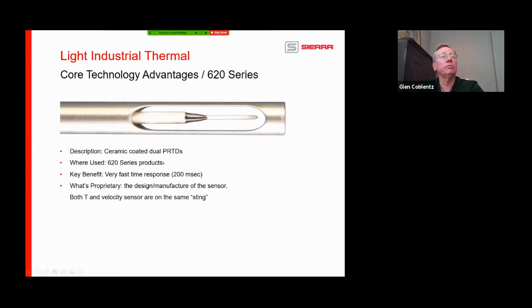Here's the ceramic sensor. Okay, it's kind of a stacked RTDs, but one of the things is it's very fast, incredibly faster than our legacy products and the Quadratherm. So if somebody needs to make a very fast measurement, this is a great way to go. You can use this all the way down to a 1-inch pipe. We have had some people put it in a 3/4 inch T, and it's worked well there. It's worked there as well.